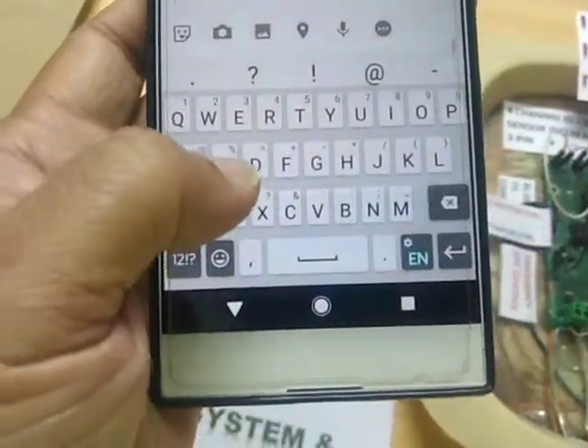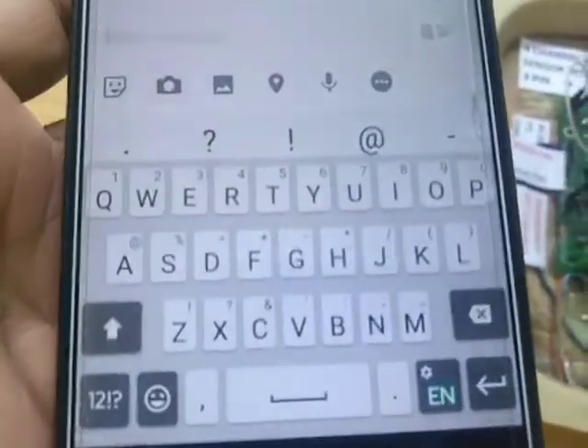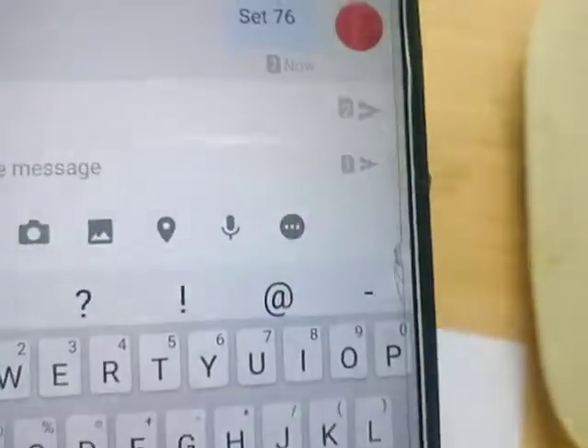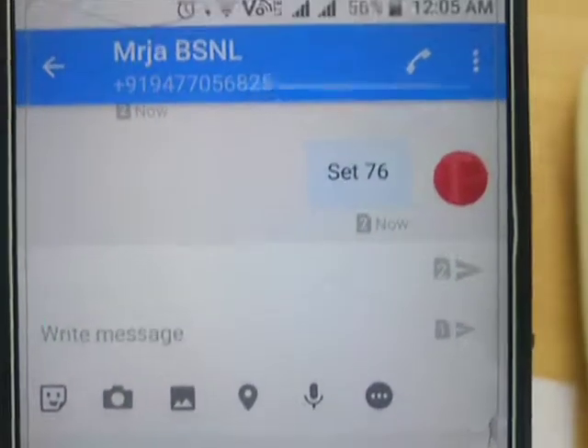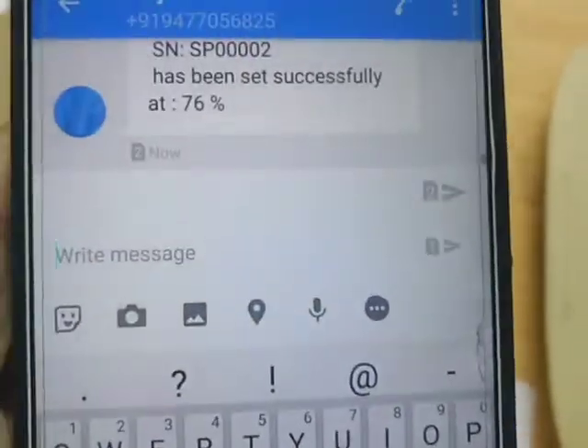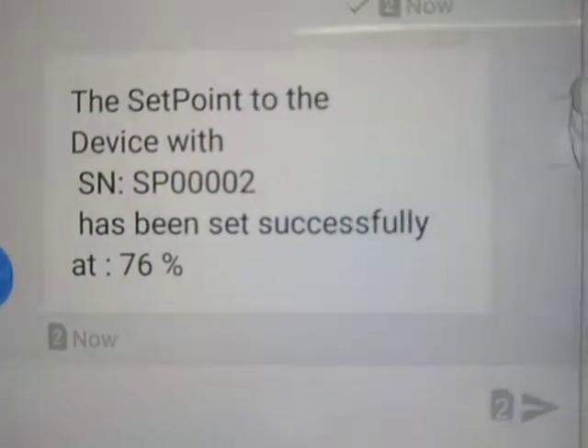So I will simply give a set point. Don't worry about the case — it's not case sensitive. I will type 'set' followed by a space and give the value as 76, and send it back. I have sent a reply saying 'set 76'. Now the device should respond with a message that it has been done successfully. You can see: the set point to the device with number SP00002 has been successfully set to 76%.